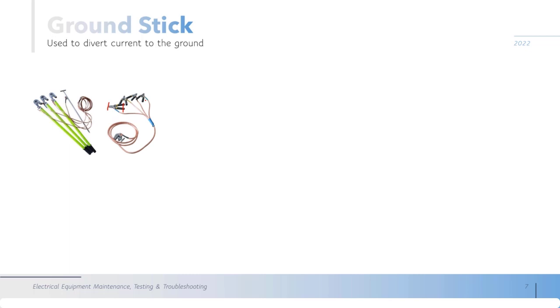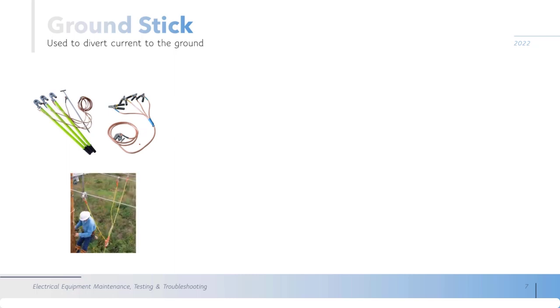So if you touch the neutral you can get electrocuted. So that's why you also discharge the neutral for your own safety. So this is used in motors, transformers of low voltage. So you can see here he's working in a low voltage line or a distribution line with a voltage of less than 11 kV. So you can see that the technician places this part in the line and in the other wires, so he grounded.